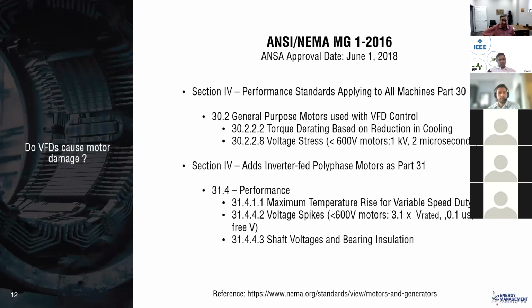When you go to the Part 31, you get a little bit more specific, saying that there still is temperature rise associated with variable speed duty. And just as a side note, when we apply an inverter on like a pump or a fan, the variable torque nature of that reduces the load so much that we don't worry about turn down ratios or those kinds of things. As a matter of fact, we see the skin temperature of a typical machine go down when the speed is reduced, because you're reducing it by the cube of the speed, typically the power plus losses. The next, and the 2 parts I think that we're addressing here now are these voltage spikes.